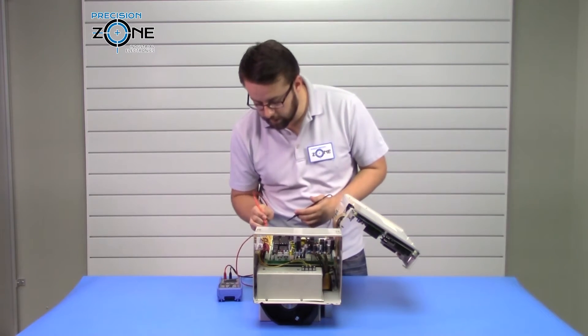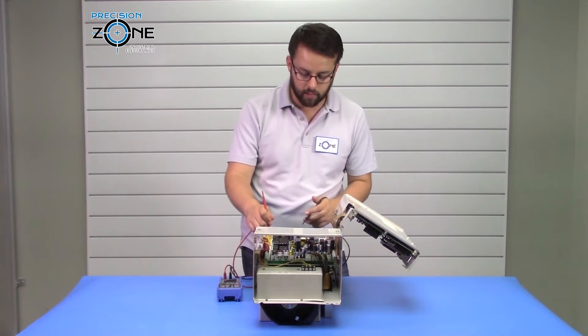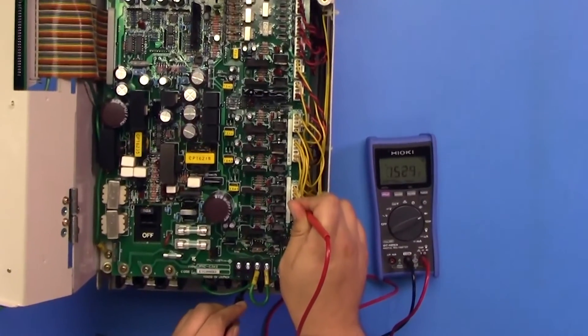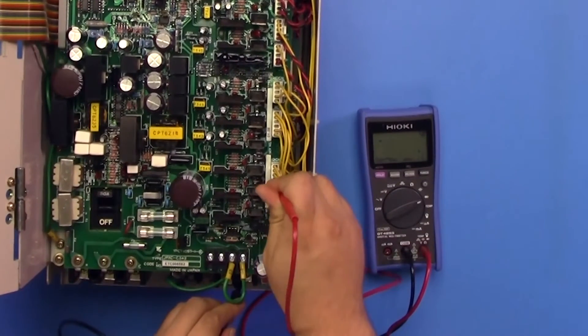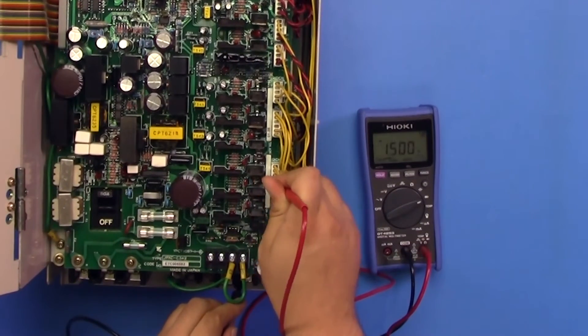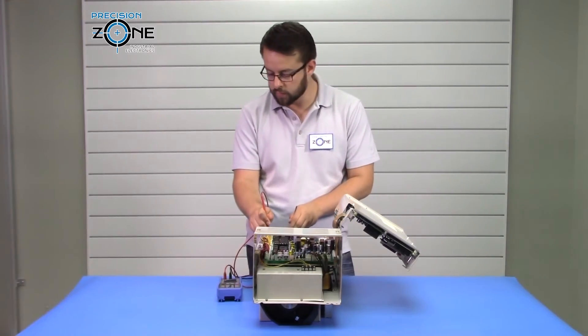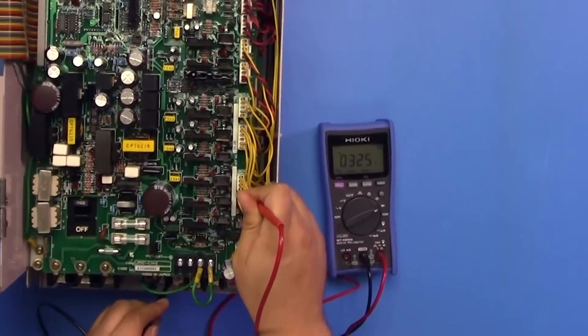Connect that to the negative pin over here, which is connected to the negative side of the DC bus. We're going to be able to check UVW, and that should be about 0.32 volts on each leg from UVW for your outputs.